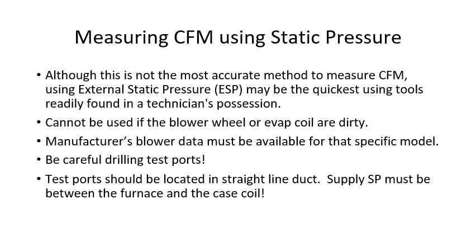Supply static pressure has to be between the furnace and the case coil. So even though it may be easier to drill a test port after the case coil in this case, the case coil has a pressure drop on it, and that's not going to give you an accurate reading. You have to drill that test port between the furnace and the case coil, and of course be very careful in doing so.